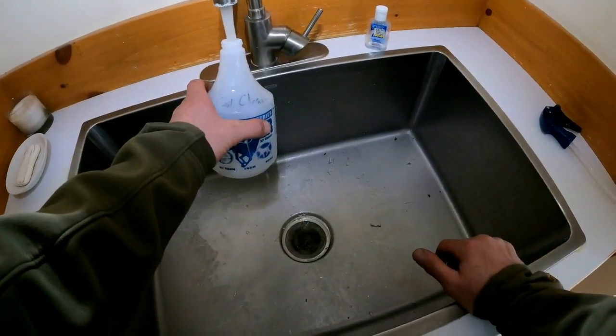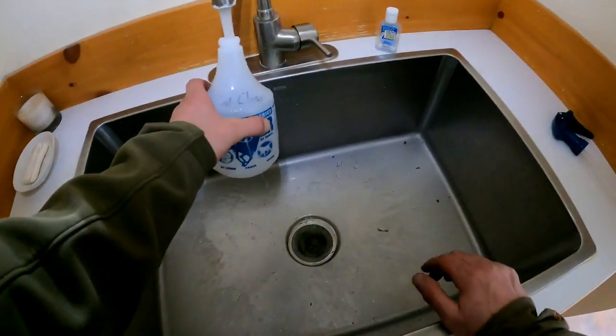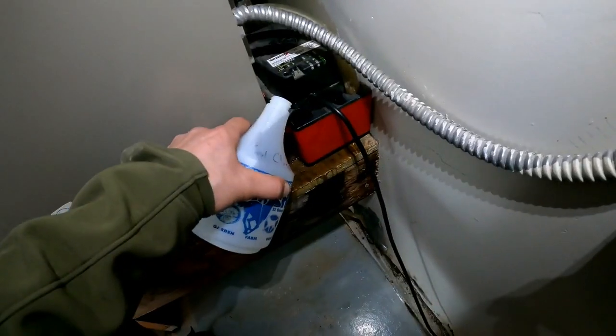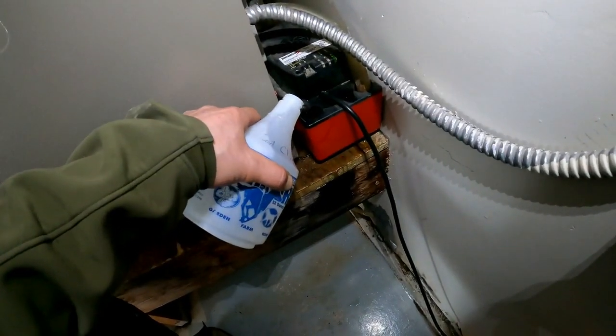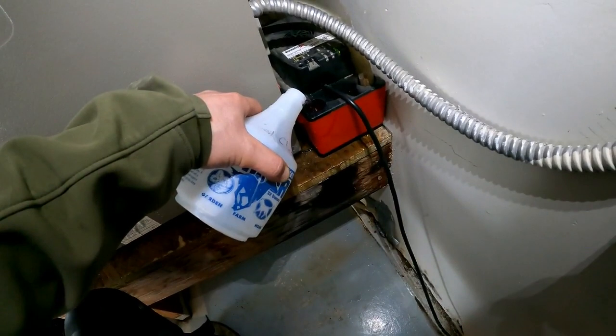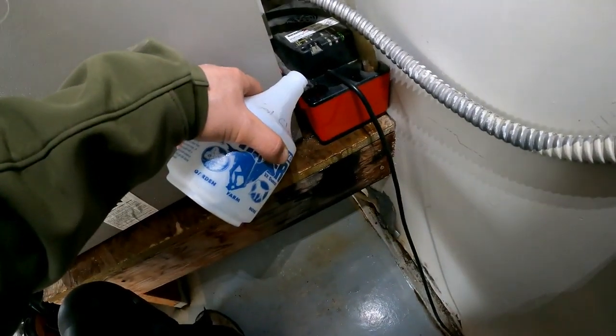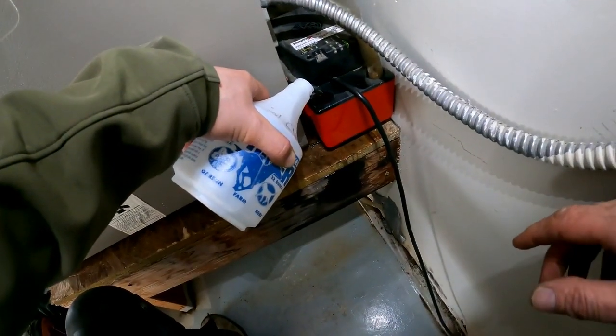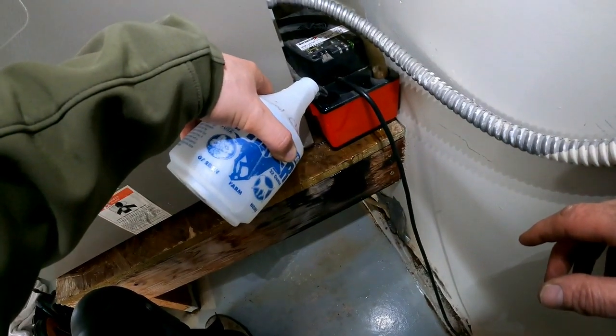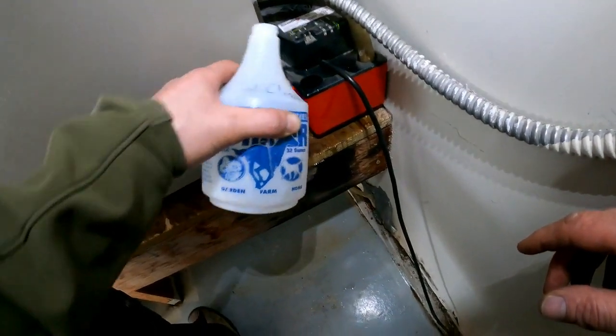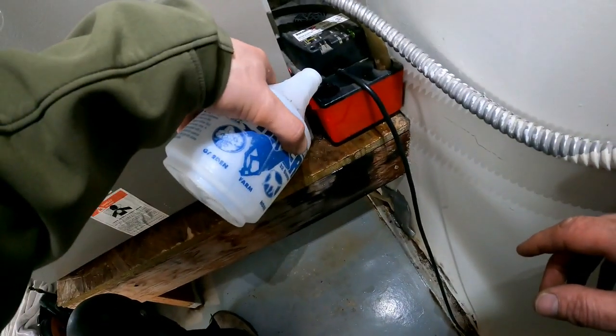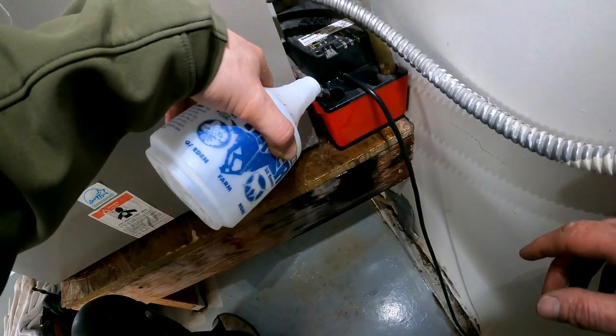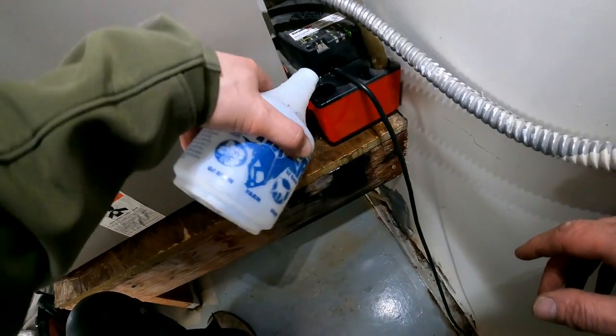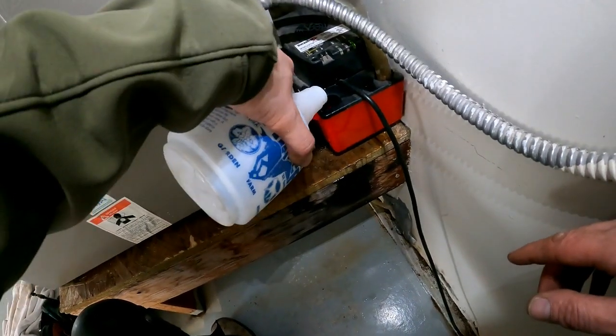I want to see if it leaks out of the pump somewhere I just can't see, or if the water level drops. We'll fill it up a ways, but not enough for the pump to come on, and then measure how high the water level is, to see if it's draining down, like running out of the bottom of the pump.